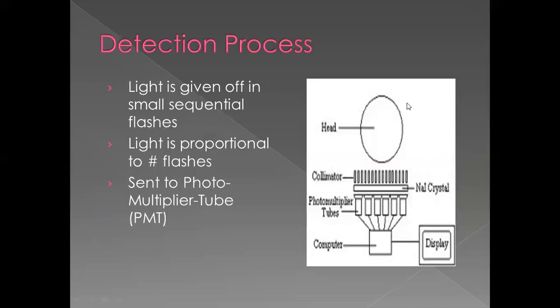Here is basically how the inside of the gamma camera looks. We have the collimator, then the sodium iodide crystal, and we have the PMT tubes attached to the crystal. Each PMT tube is very close to the next one — any gap between PMT tubes will cause artifacts in our image.